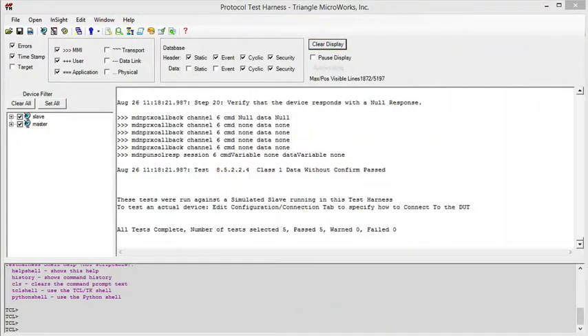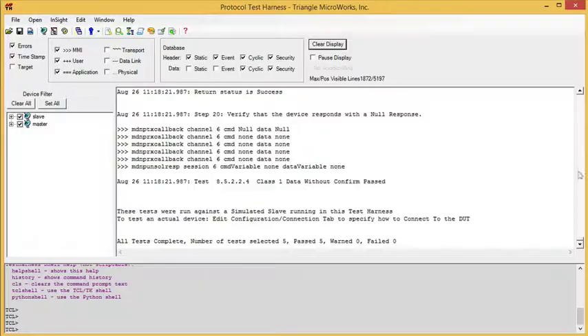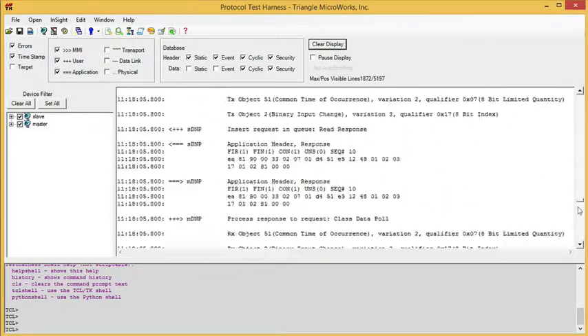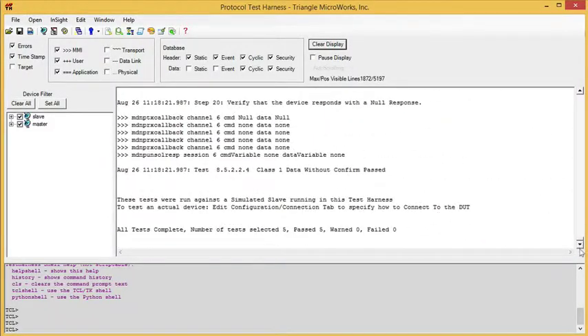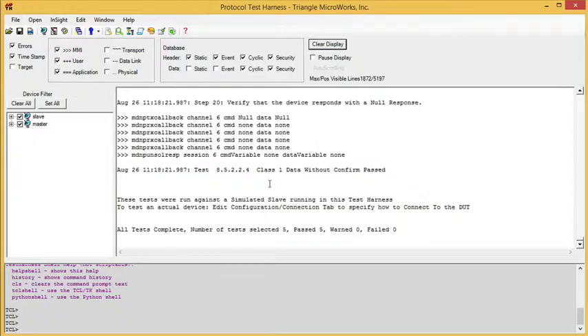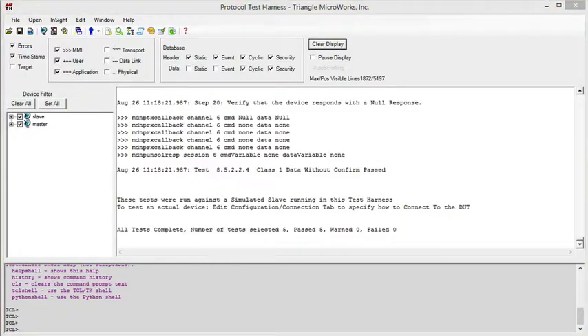All of this is also logged in the Communication Protocol Test Harness protocol analyzer log. So at the conclusion of your test, you can save out this log, and then you can review it to make sure you understand the test results, and you can submit it to the DNP3 users group for verification of your conformance.